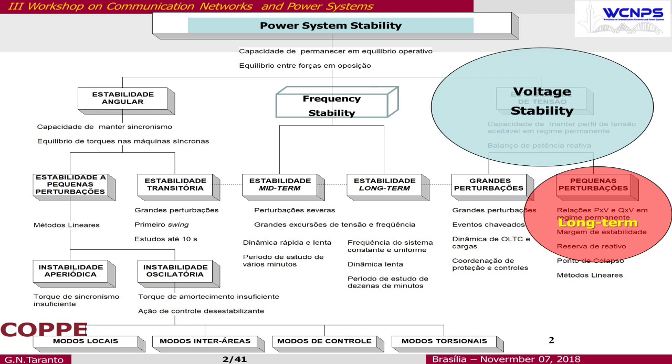will run from seconds to minutes. Which means that you can have intervention from the operator, for instance. It's very important in this kind of instability to model OLTCs and OEL, over-excitation limiters. And the idea is to find the maximum loadability point in the famous nose curve. This is what we're trying to identify based only on measurements.